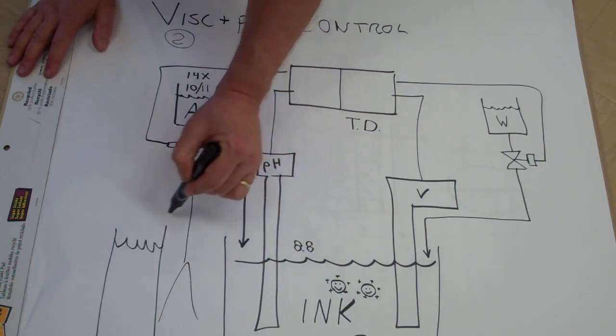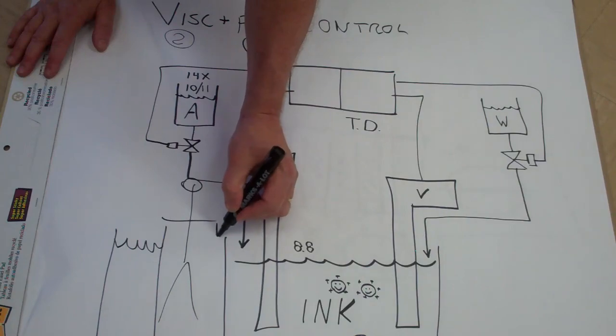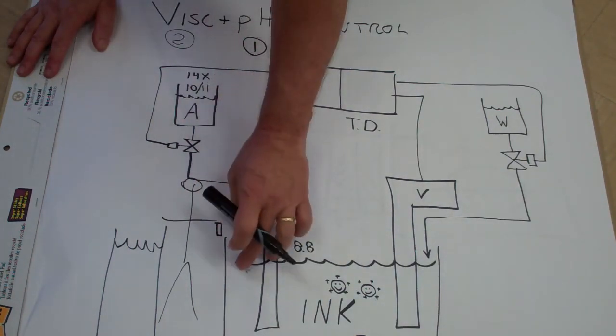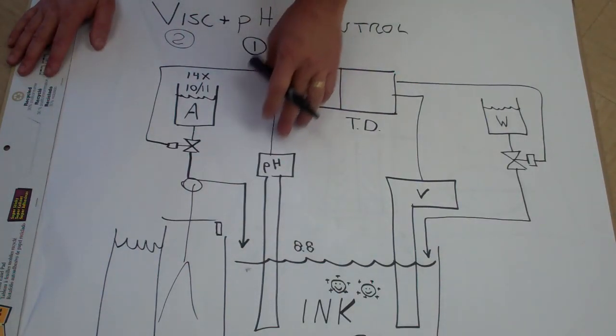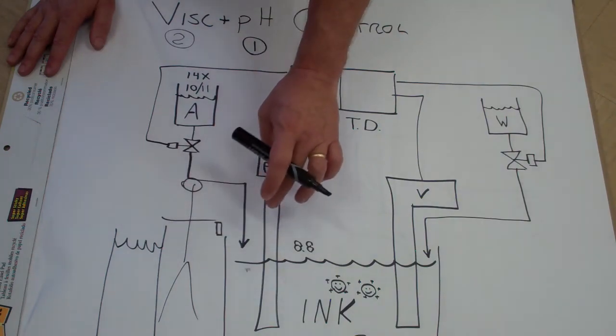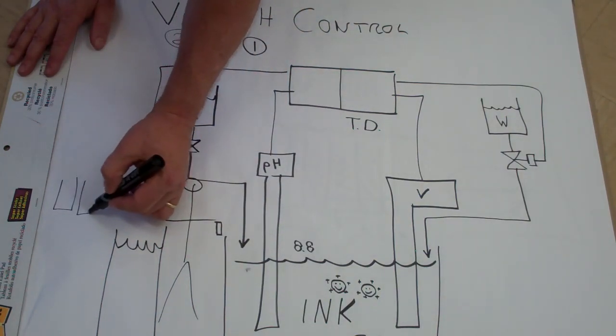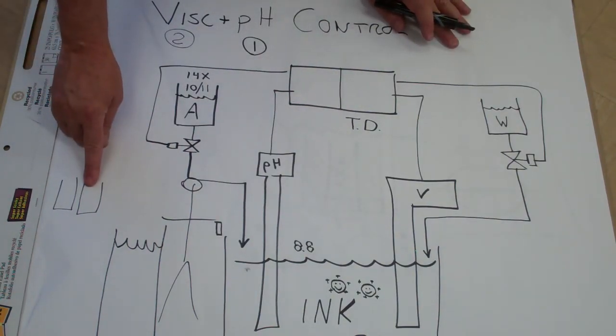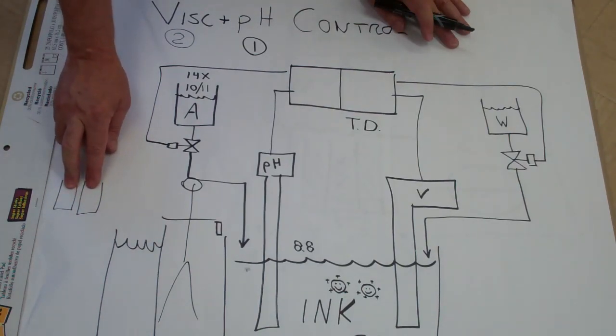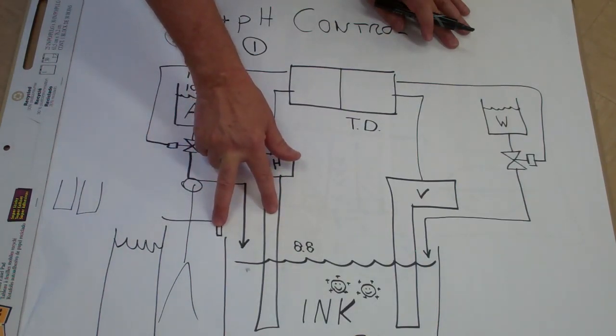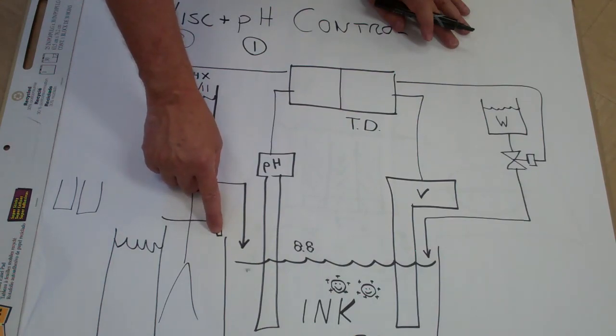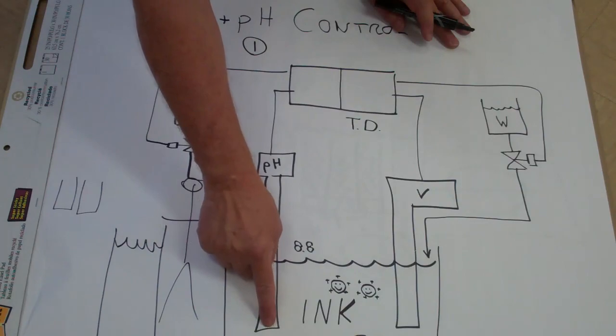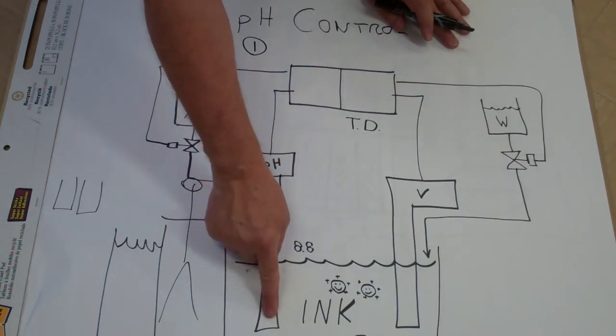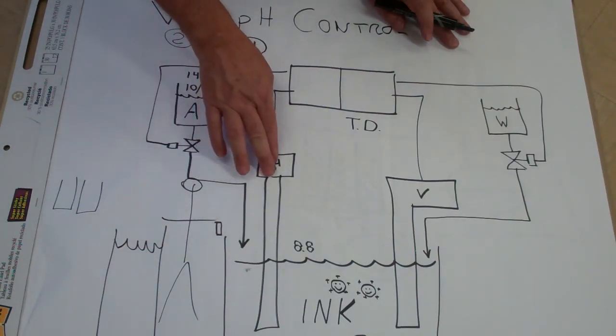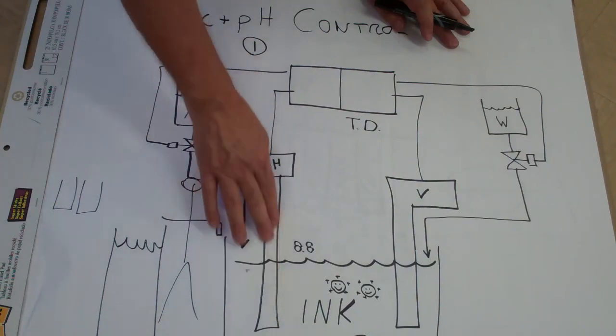You're going to have an operator here. He's going to have a little pH sensor that he dips in the ink to check the pH manually. These have to be synchronized up. You can calibrate this and this together on the same two buffer solutions. Buffer solutions age with time. Once you open the bottle from the supplier, they begin to decay. You have to change those on a regular basis. You have to recalibrate on a regular basis. And just like on this, there's a cap on the end. That's to keep it wet. You gotta keep this end wet. There's no cap to put in it because you're in a tank. That's why you put it in a standpipe if you're using the in-tank type sensor.